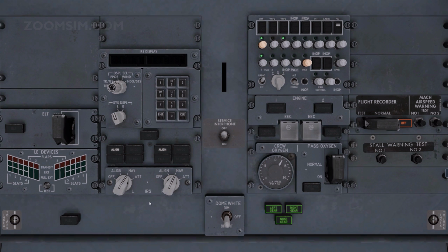The on DC light indicates that the related IRS is operating on DC power from the switched hot battery bus. The align light illuminates steady when the related IRS is operating in the align mode, the initial ATT mode, or the shutdown cycle. The align light flashes if alignment cannot be completed due to a significant difference between previous and entered positions, or an unreasonable present position entry, or no position entry.